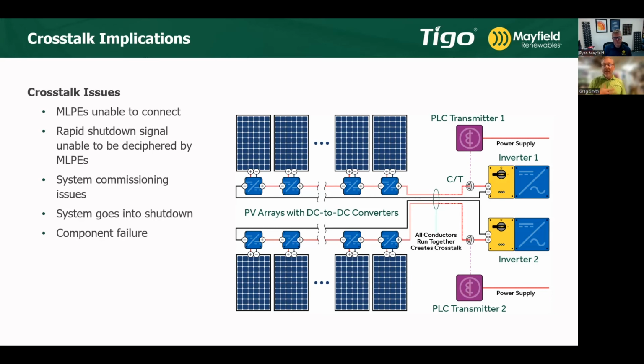I think it's fun to troubleshoot these things. We send people out to these large sites because there's a lot at stake—you've got 250 kilowatt, 1 megawatt, 5 megawatt, 12 megawatt systems. People want answers, and it doesn't look good for our industry when things burn up. So we're not trying to assign culpability or say it's your fault—that's not what we're trying to do. We're just trying to get to the bottom of it. And if it's something that falls on us, we're going to own up to that. But we also expect the same kind of responsibility from the installers. If you didn't know about this crosstalk thing, that's just ignorance, and that's fine—you can fix ignorance. That keeps you and me gainfully employed.